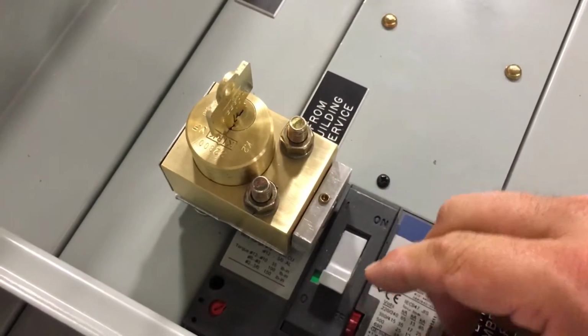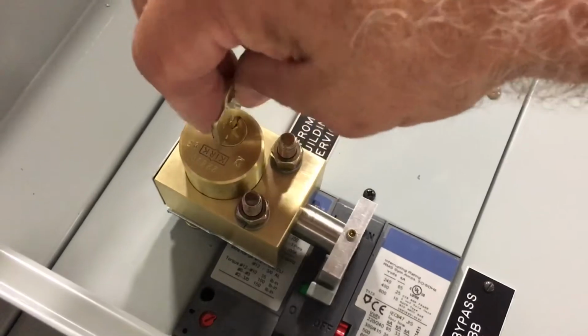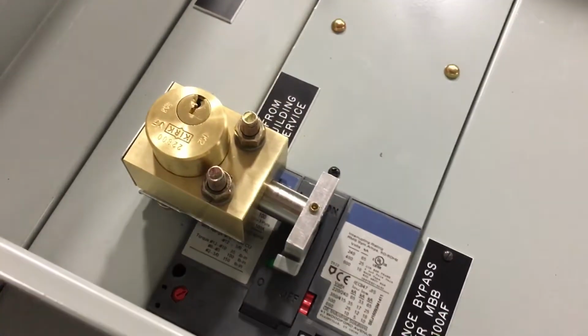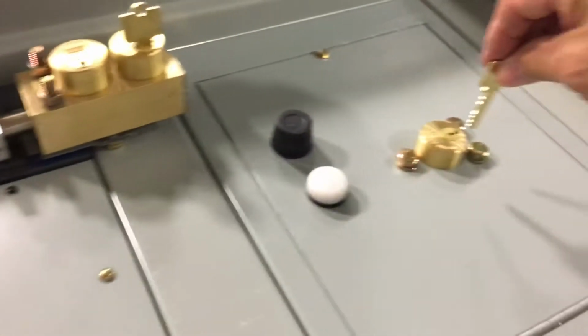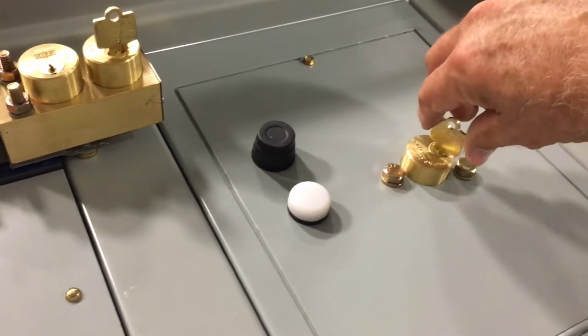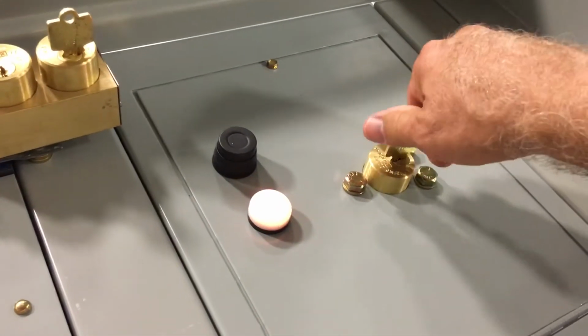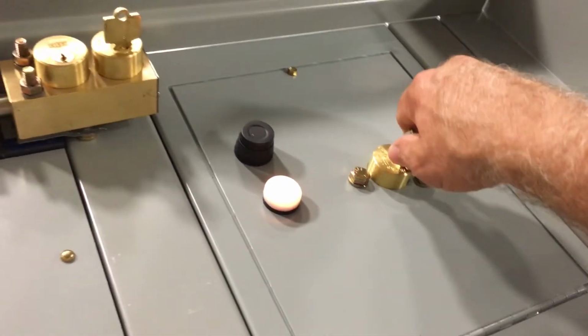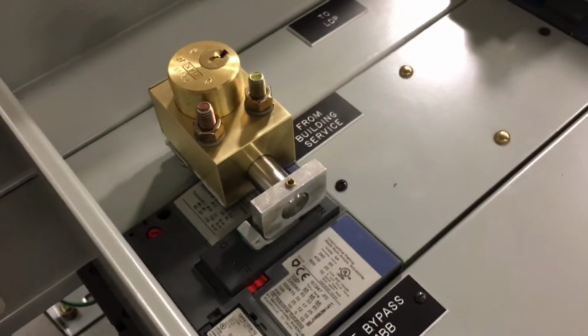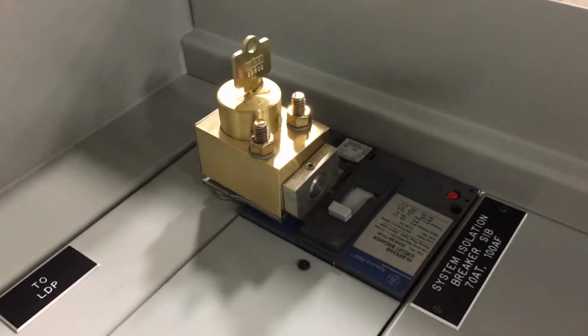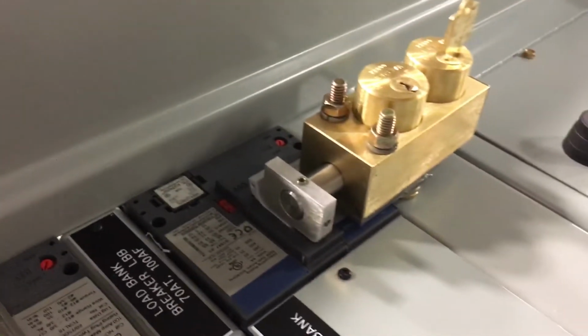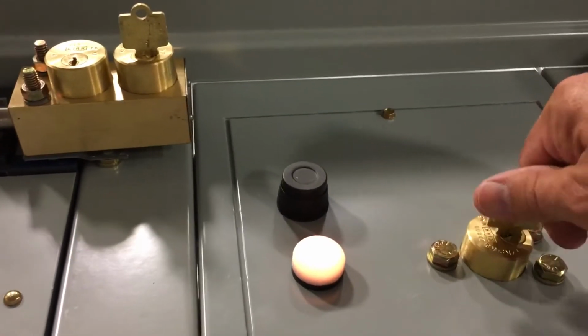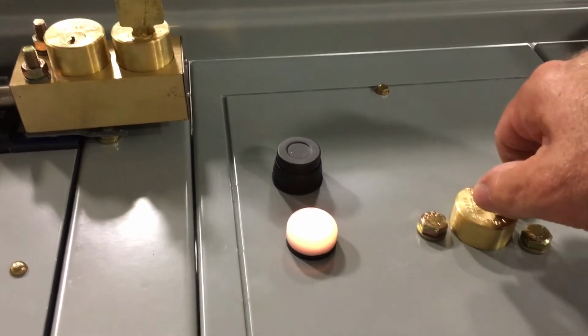open MBB, turn the key counterclockwise to extend bolt, locking it open, take the key out, stick it in the SKRU, solenoid key release unit, turn it clockwise, and it's locked in. We're back on normal mode. MBB is locked open, SIB is closed, load bank breaker locked open, and key K1 is locked in the SKRU.